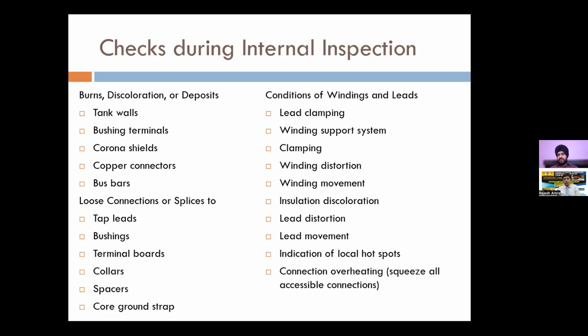And if there are any loose connection or splices, in some cases where transformer is feeding a lot of downstream faults, we have seen OLTC leads also getting loosed, the bushing leads getting loose due to improper fitting of corona shields. Then terminal boards can also get shifted due to frequent faults. So all these loose connections and burns, discoloration, then condition of the winding, whether winding has shifted compared to the other windings. So all these points also you need to record properly. And like I said earlier also, it is very important that the first person who enters, he is very much meticulously recording everything, so that it is beneficial for others also.